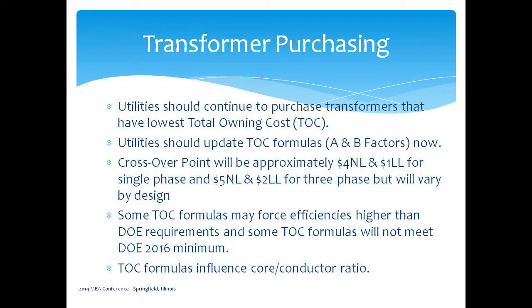If you're looking at purchasing transformers, got any buyers in here or people that recommend to buy? Not too many? Well, y'all probably don't care about this, but you can go stump your purchasing agent the next time you see them, because they may be asking you for this: look at A and B factors. That's kind of been a rule of thumb. If you know your A and B factors, which indicate your no load and your load loss characteristics, it allows manufacturers to actually design an optimal transformer for your operation. And that'll tend to, I won't say skew, but it'll certainly change the design enough so it'll give you exactly what you're looking for.